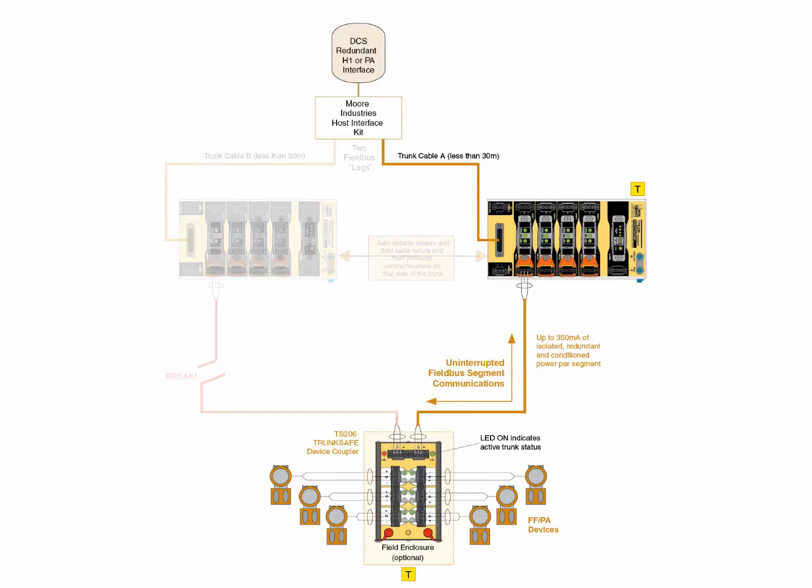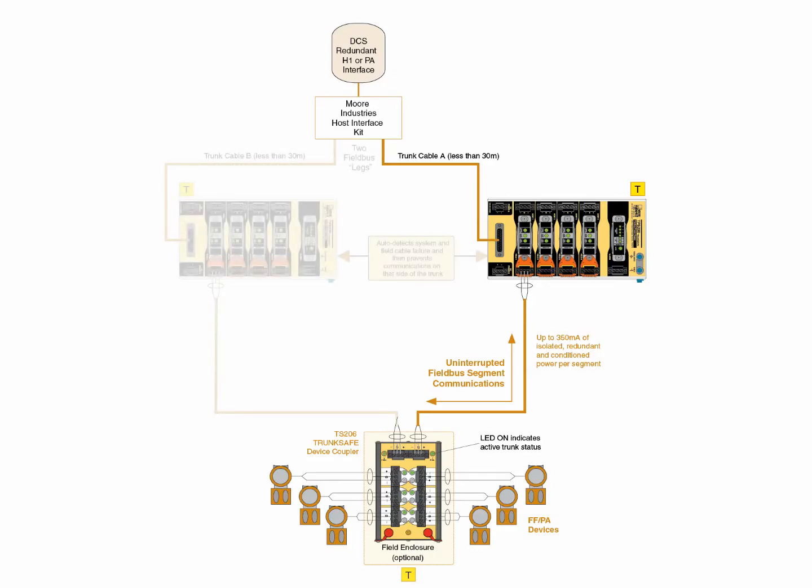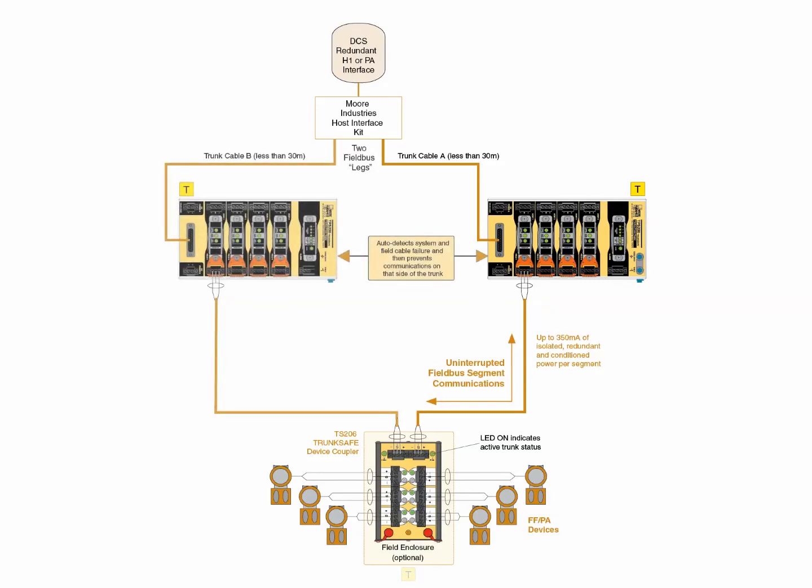The device coupler's auto-termination feature, along with the power conditioner's fault-sensing capability, allow field bus communications to remain uninterrupted on the healthy leg. Once the fault is removed, the device coupler and power conditioner automatically return to their pre-fault condition and clear the segment fault alarm.